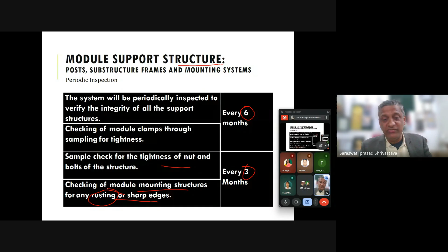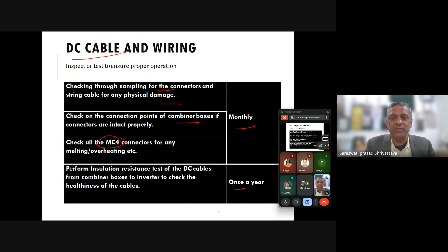Now, DC cable and wiring inspection, monthly as I told in the first slide, and some things only once a year. You need to check sampling connectors, physical damage, and combiner box, and MC4 monthly. Other than this, checking insulation in the DC cable is only once a year. The IV curve check can be done later as well.